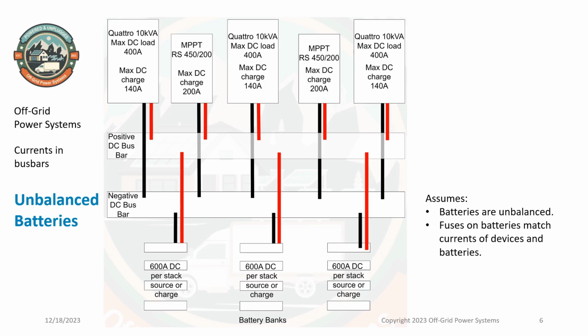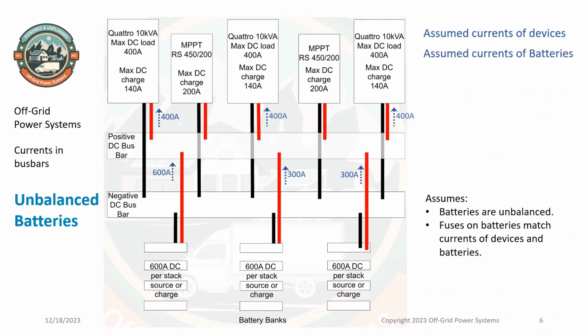What happens if the batteries are imbalanced? Or if there are differences in the connections to the bus bar? By the way, we recommend that identical wires in length and size are used to connect the batteries, and similarly, Quattros and MPPTs to minimize imbalances. Again, we start with all Quattros requiring 400 amps. Now the batteries are extremely imbalanced.